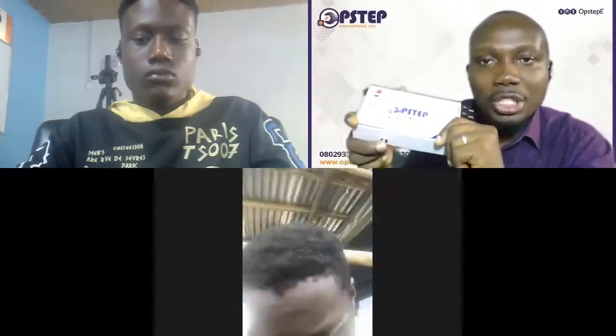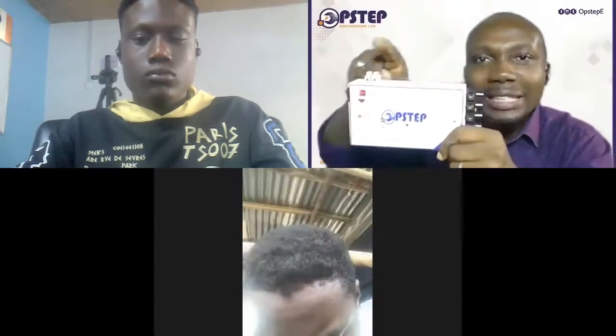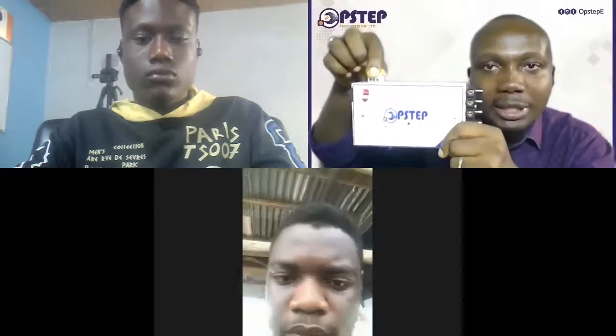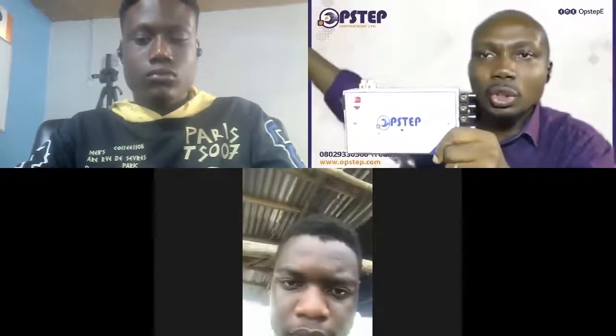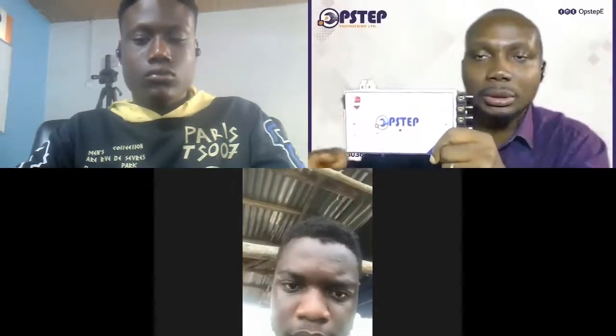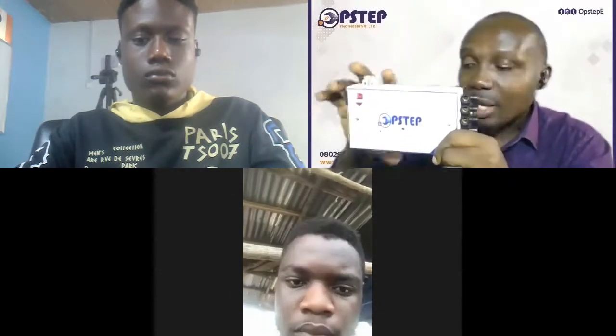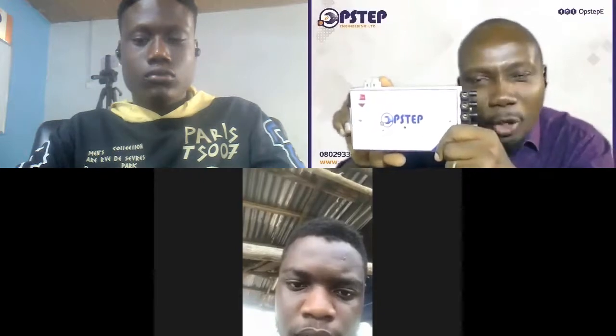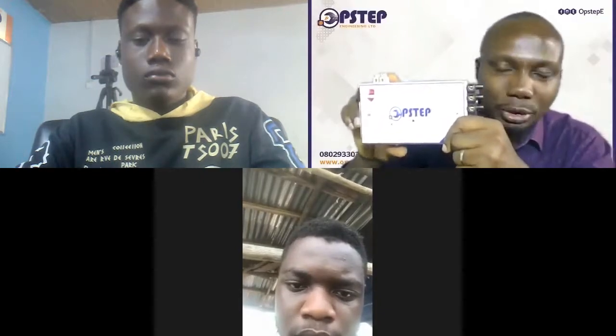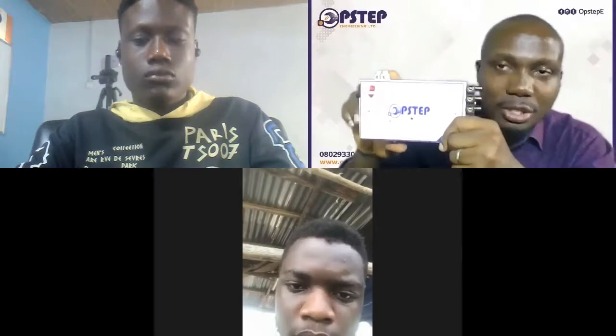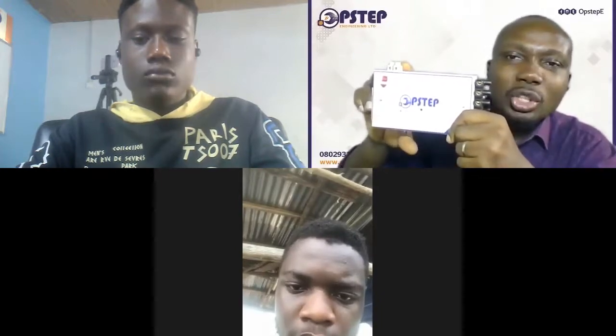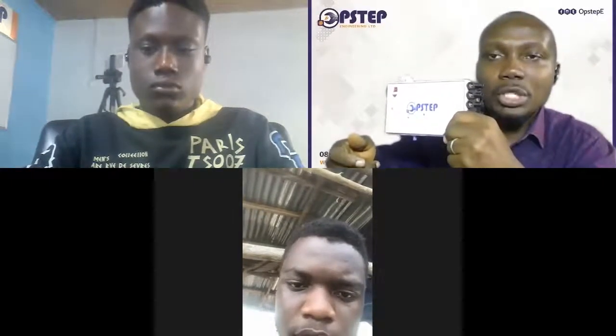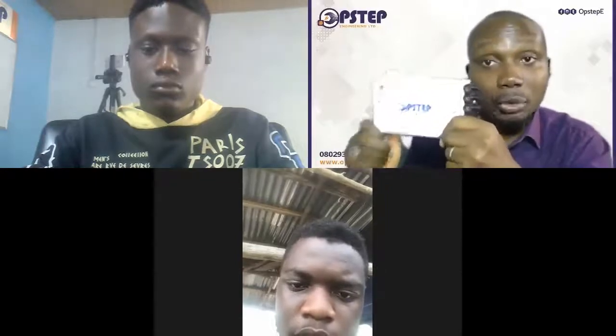Because this switch is directly connected to this output, to this connector point that goes into your generator on-off switch. So if you get wire from the generator on-off switch and connect to this place, when you press down this switch, it carries out the same function as though you have gone to the generator set and flipped the on-off switch to the off state. So that's what it does.